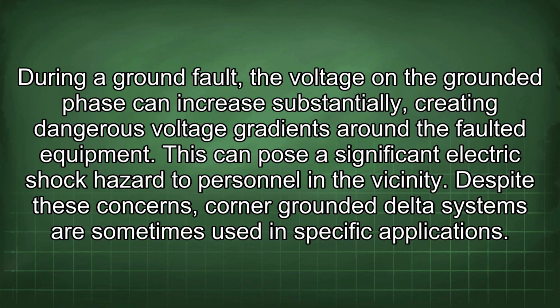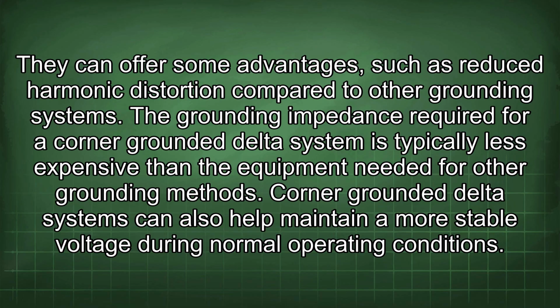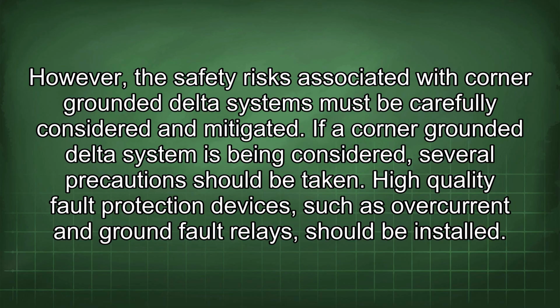Despite these concerns, corner-grounded delta systems are sometimes used in specific applications. They can offer some advantages, such as reduced harmonic distortion compared to other grounding systems. The grounding impedance required for a corner-grounded delta system is typically less expensive than the equipment needed for other grounding methods. Corner-grounded delta systems can also help maintain a more stable voltage during normal operating conditions. However, the safety risks associated with corner-grounded delta systems must be carefully considered and mitigated.